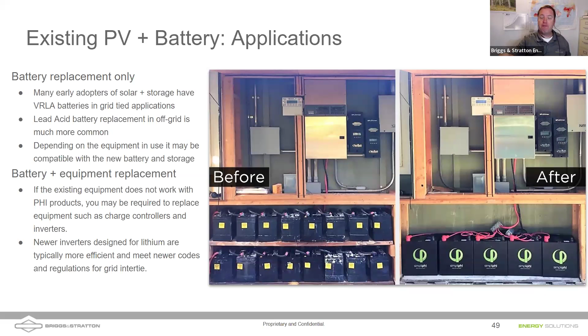Steve Pitney made a good point here: for off-grid, they generally bring their 26K generator right into the grid terminals. In fact, off-grid, you don't need to use that generator port. You can actually use it for load shedding on a Sol-Ark 15K, because Sol-Ark recommends that you bring your generator into the 200 amp gen port. So in an off-grid situation, we should probably customize that slide a little bit for the off-grid talk. But thank you, Steve, for pointing that out.